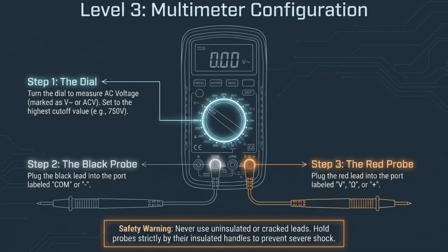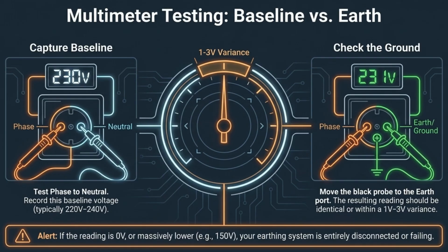Level 3 involves using a multimeter. Set your dial to measure AC voltage and insert the probes into their respective ports. Always remember to use insulated leads and hold them by the handles to prevent any risk of severe shock. Using your multimeter, measure the voltage between phase and neutral to establish your baseline. Then, move the black probe to the earth port. The reading should be very close to your baseline. A 0 or significantly lower reading indicates a failure.